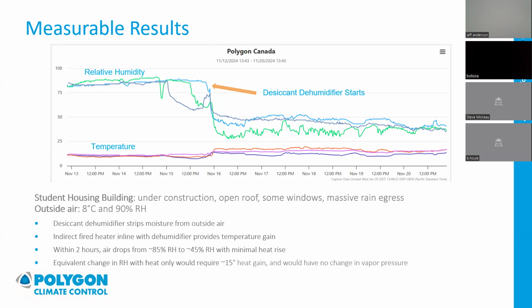The other thing to point out is that your average permanent equipment won't actually have a desiccant dehumidifier in it. Your rooftop may have a dehumidification feature from the air conditioning, much like those little portable units. So they can sometimes remove some moisture, but the moisture load you can create during construction is potentially much, much higher than a permanent system could actually remove anyway.